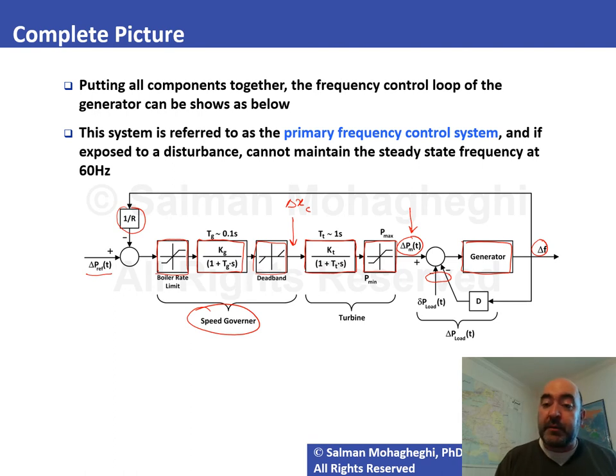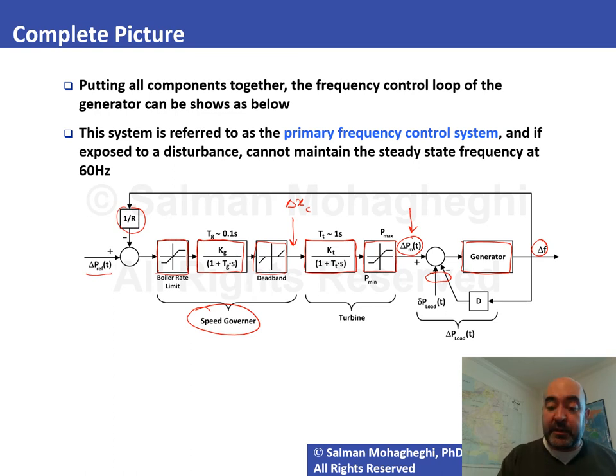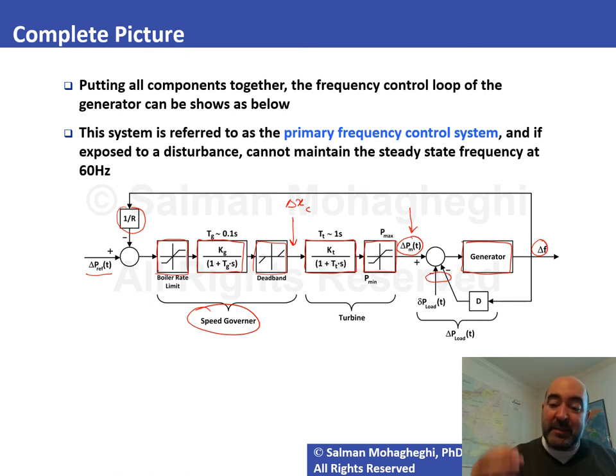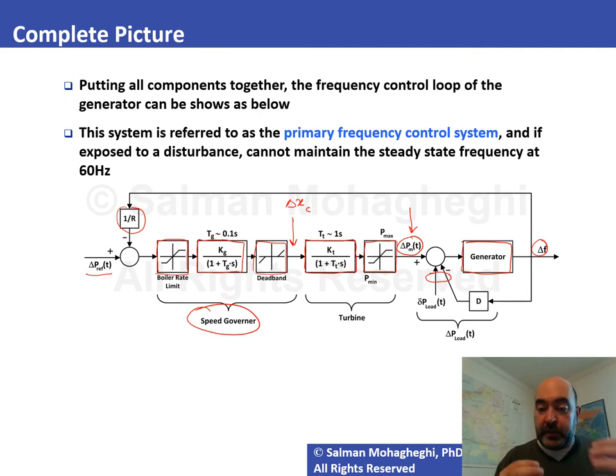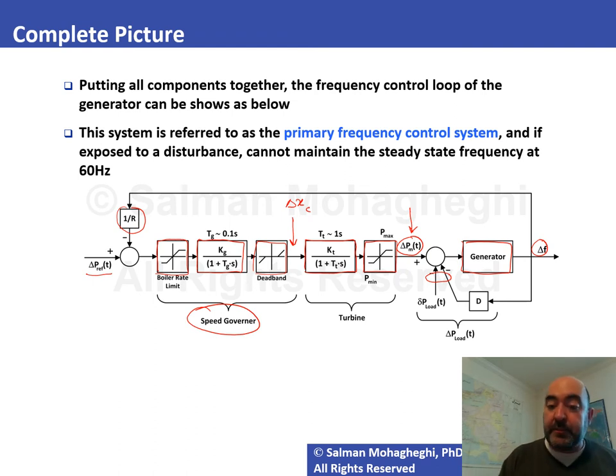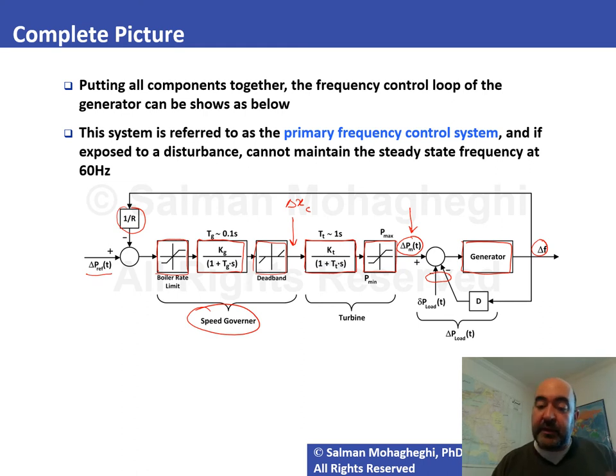This is known as the primary frequency control system, distinct from the secondary frequency control system (AGC). On its own, the primary system cannot restore frequency exactly to 60 Hz — it responds within a few seconds and brings frequency closer to 60 Hz, then waits for AGC to kick in. AGC operates on a minute timescale and is responsible for restoring frequency precisely to 60 Hz.